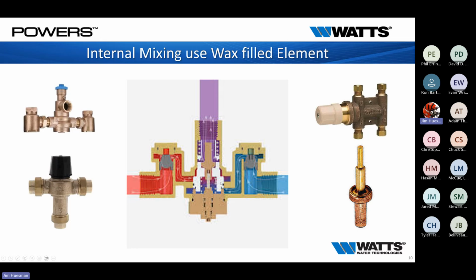If this was just an open range, half our pipe would be cold, half would be hot, especially if we're like a 75-25, most of it's going to be cold with a little hot. So it doesn't mix till it gets pretty far down the line and blends together. So we've got to figure out how to blend it, keeping all these features in here to really mix that water, because we need it mixed right outside the valve. We don't want it blending 10 foot down the line, we need it to hit that desired temperature as soon as we leave that valve.